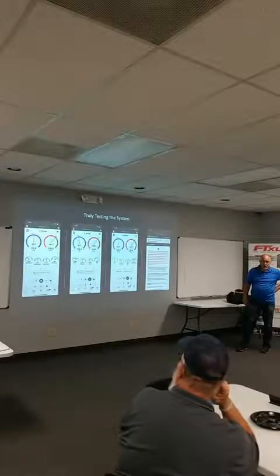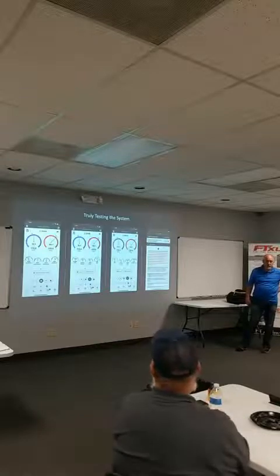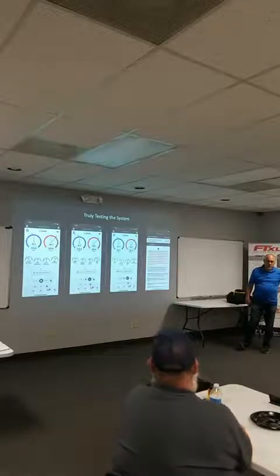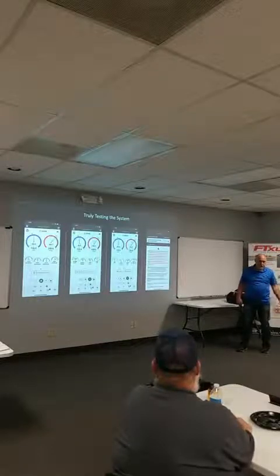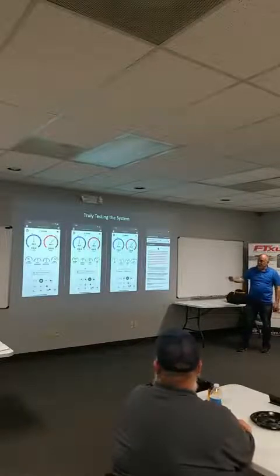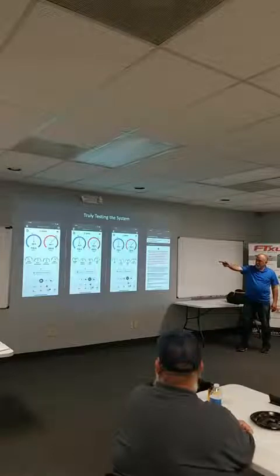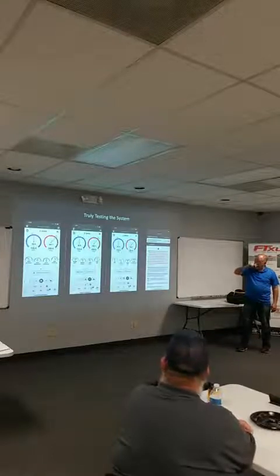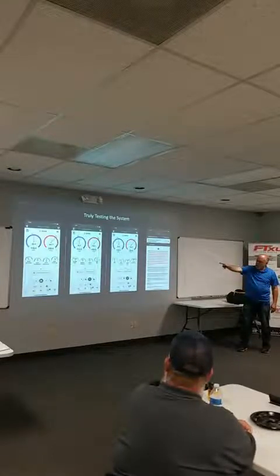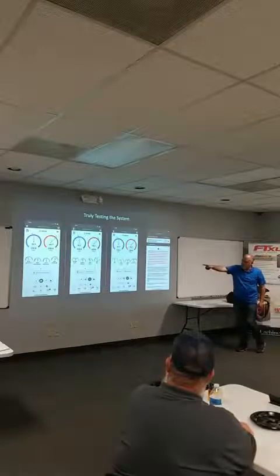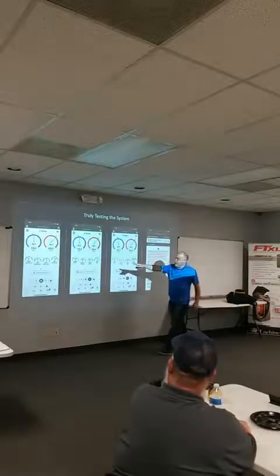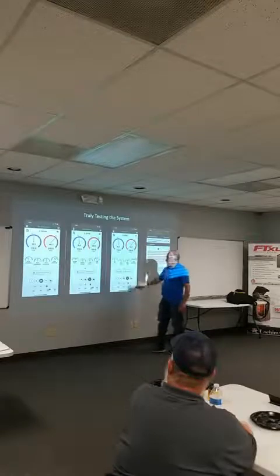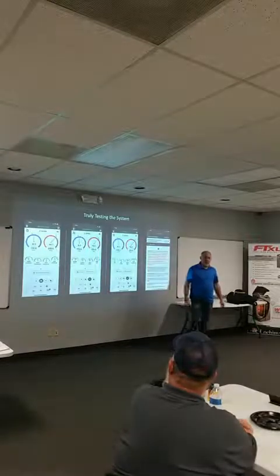This was all sensible heat gain due to an uninsulated return air chase in the attic. So somebody handed it over, but nobody insulated it. So it's just picking up heat. That's all it is. And the humidity in there, I can't remember why it stayed at 50, because it normally would have dropped down. It may have had some other leakage in here, but here's all I want you to see. That 36,000 BTUs dropped down to 24,000 BTUs, and we went from 13 to 10 SEER on this here.